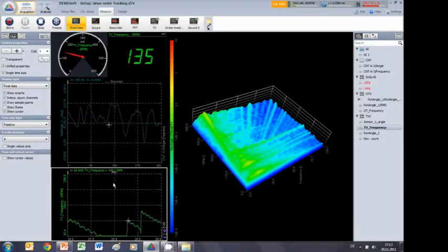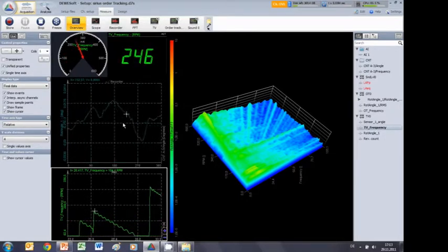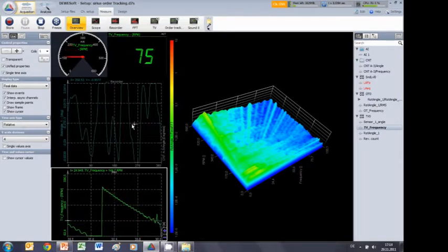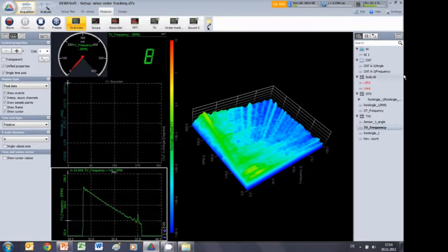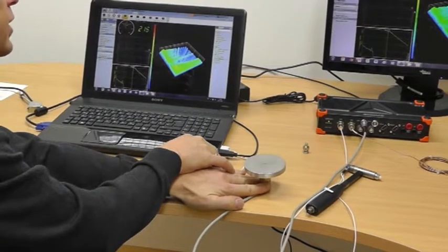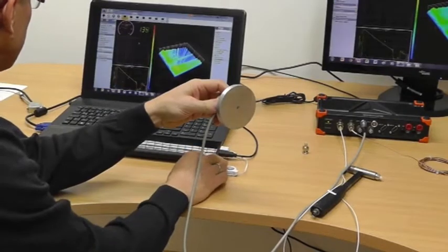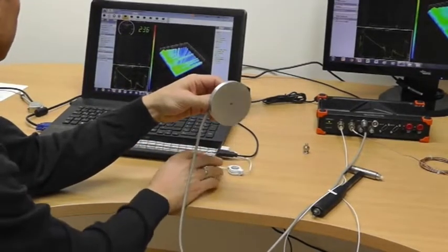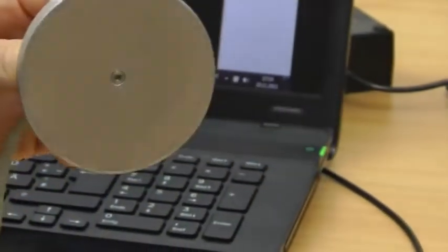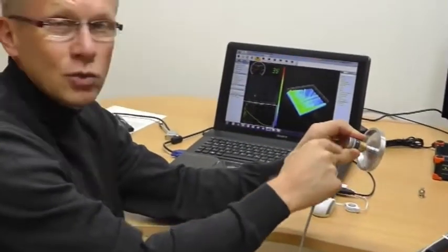So this is a time-based measurement. Here I can show an angle-based measurement from zero to 360 degrees. And you see if this would be stable, then the variance of the RPM is very little. You see here. If I move it to this 90 degree, then you see the variance of the RPM during one revolution. It's very high. So this is what we call also a rotation vibration based on the unbalance of this wheel.